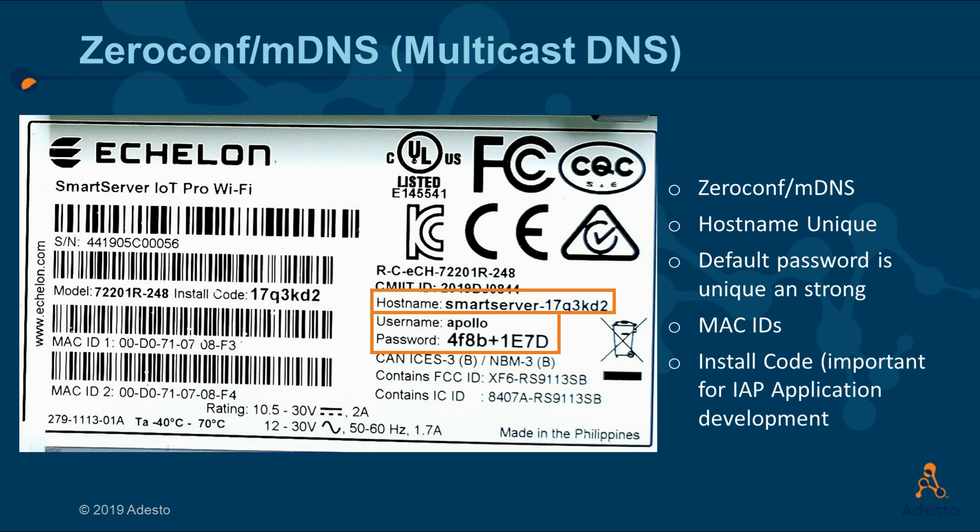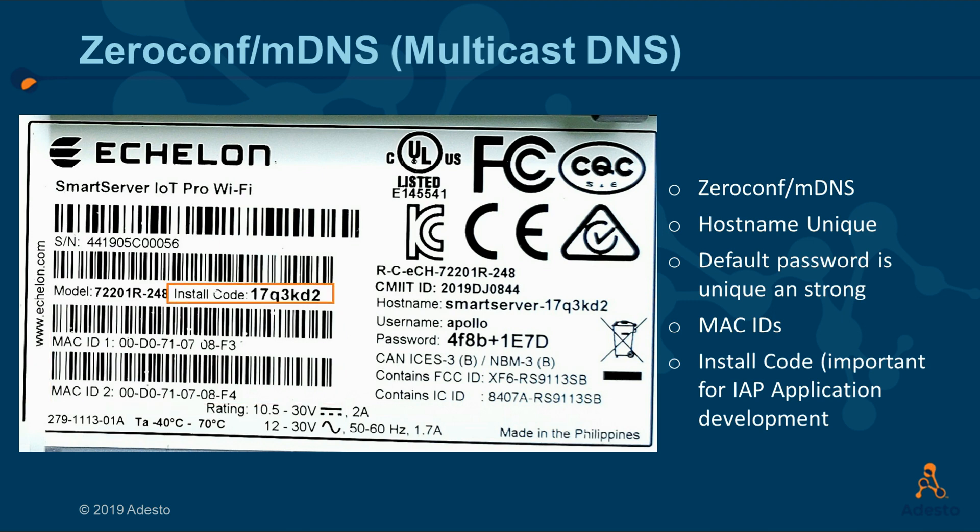You must know that in the first customer shipment there is no facility to recover a lost password. In the 2.50 release and beyond, a 20 second press of the service pin will create a period of 120 seconds for anonymous access so that the password can be changed. Also on the back you'll find the Mac IDs should you need them.